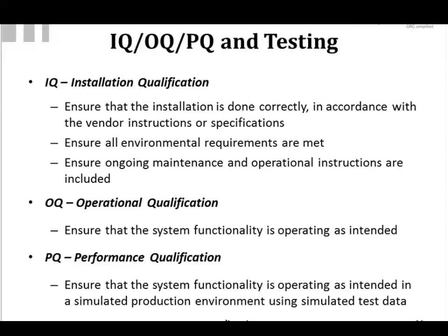And you want to make sure that you are challenging it to all levels. You're making sure that multiple users are able to log in and use the system concurrently without error. Things like that. You want to make sure that it's thoroughly tested. The difference between OQ and PQ is testing it as you would be using it, not just making sure the package does what it's supposed to do in OQ.